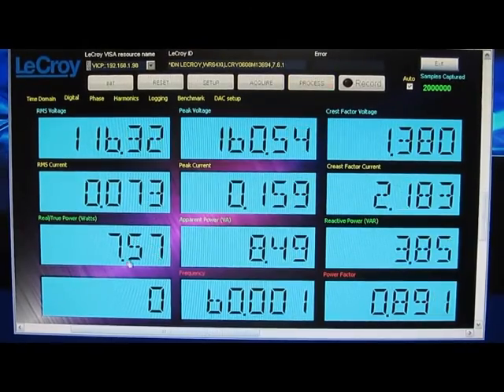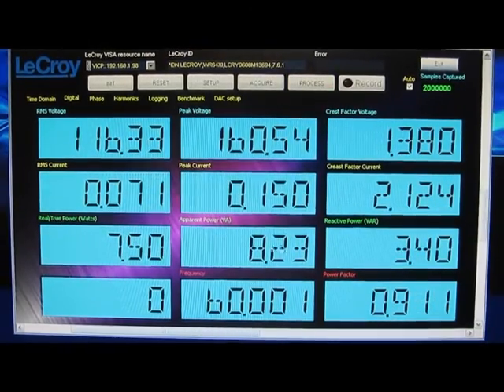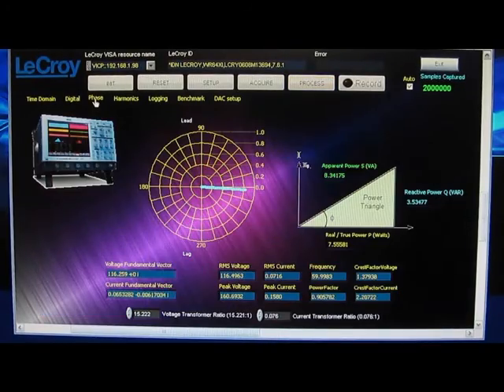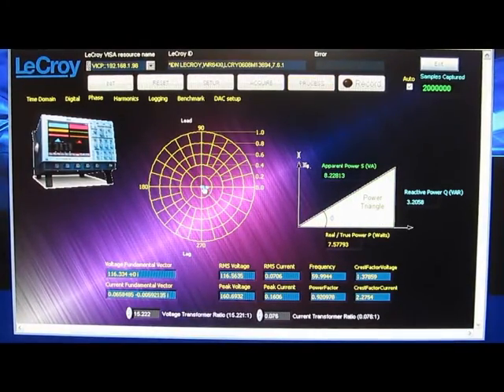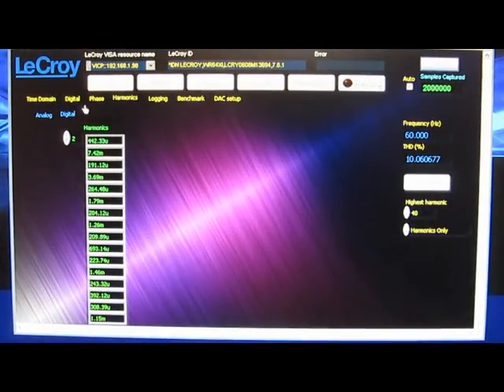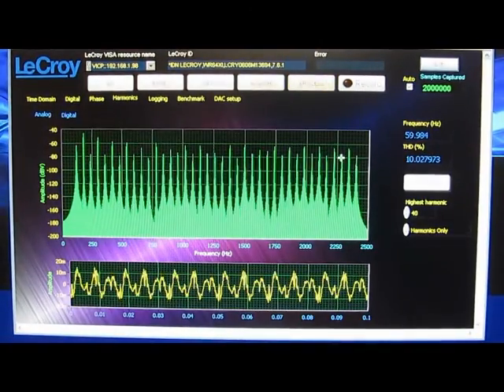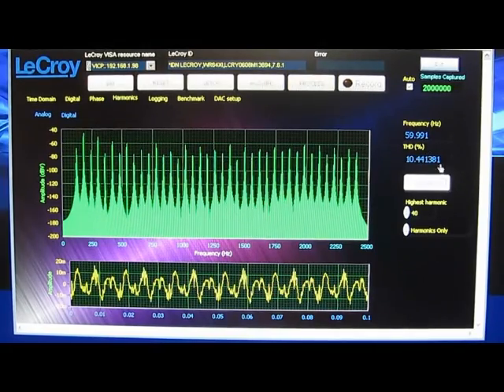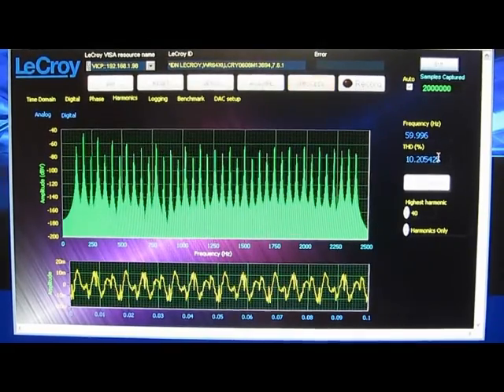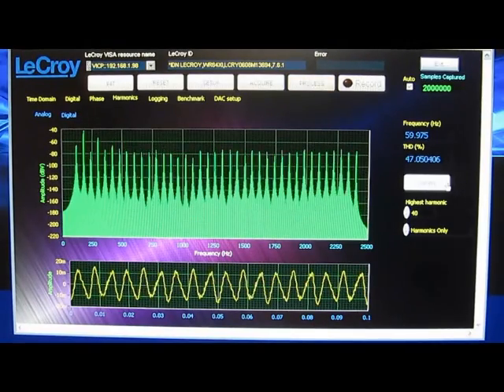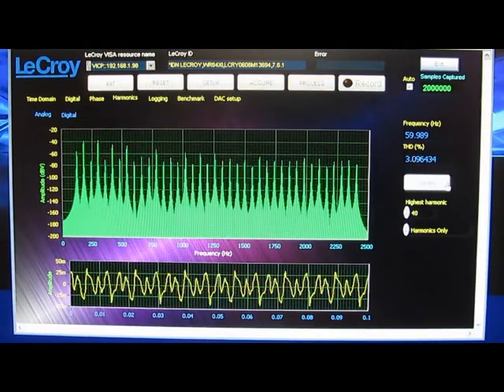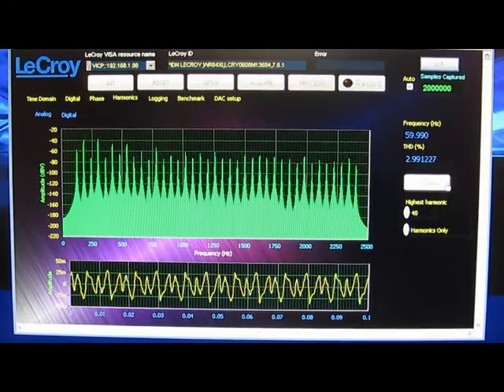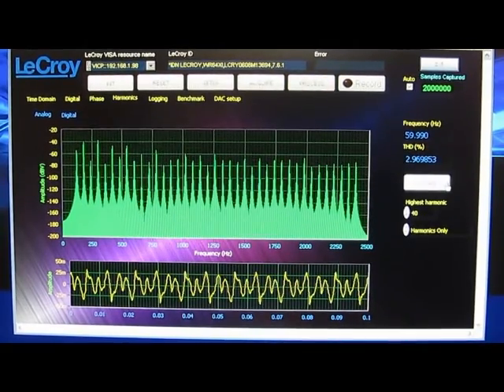Or roughly 7.5 watts, 8 watts of apparent power. And we can see the bulb itself is pretty much in phase. THD for this light bulb is roughly 10%. We compare that with our incandescent bulb at roughly 3%.